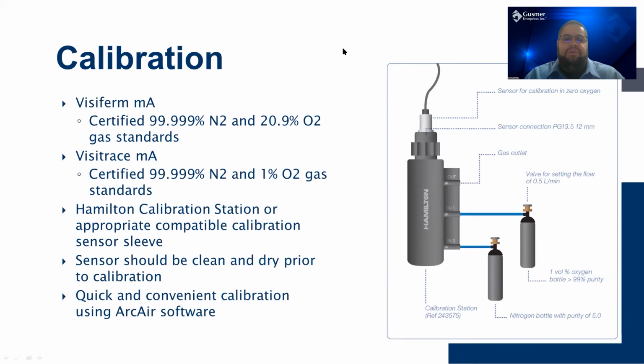The calibration of these sensors, typically you'll want to calibrate about every 3 months or so on these new Visitrace and Visiferm MA caps. It really varies depending on how much product flows through the process and how often your sensors are in use. But typically that's about correct. Previously, you'd have to calibrate once a month on the old style sensors.